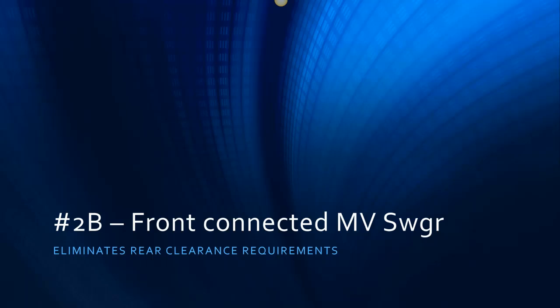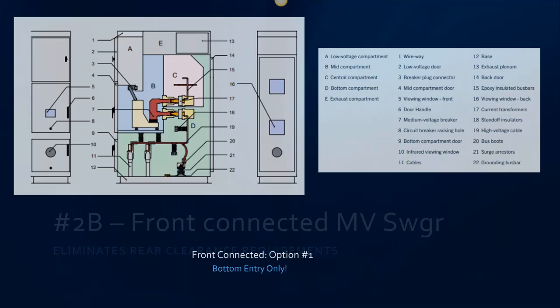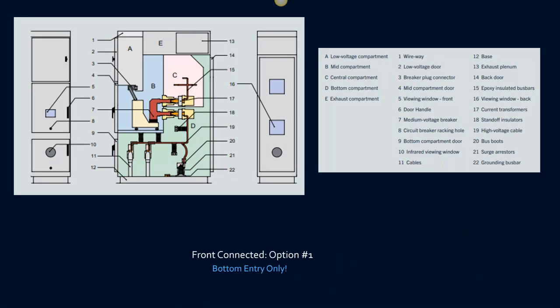One of the other solutions is front connected medium voltage switchgear. And the main advantage to this, especially in a block building, you sort of lose this advantage by going to an E-house, but in a block building, you are going to have at least 30 inches. I believe that's correct for the NEC, and I hope somebody will correct me if I'm wrong, of working distance between the rear of that switchgear and the wall, at a bare minimum 30 inches. If the switchgear is front connected, then the gear no longer requires that clearance.